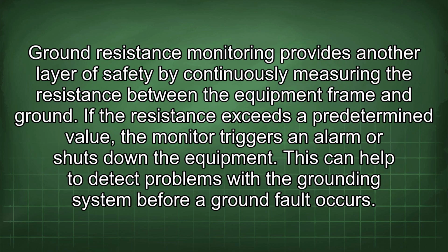Ground resistance monitoring provides another layer of safety by continuously measuring the resistance between the equipment frame and ground. If the resistance exceeds a predetermined value, the monitor triggers an alarm or shuts down the equipment. This can help to detect problems with the grounding system before a ground fault occurs.